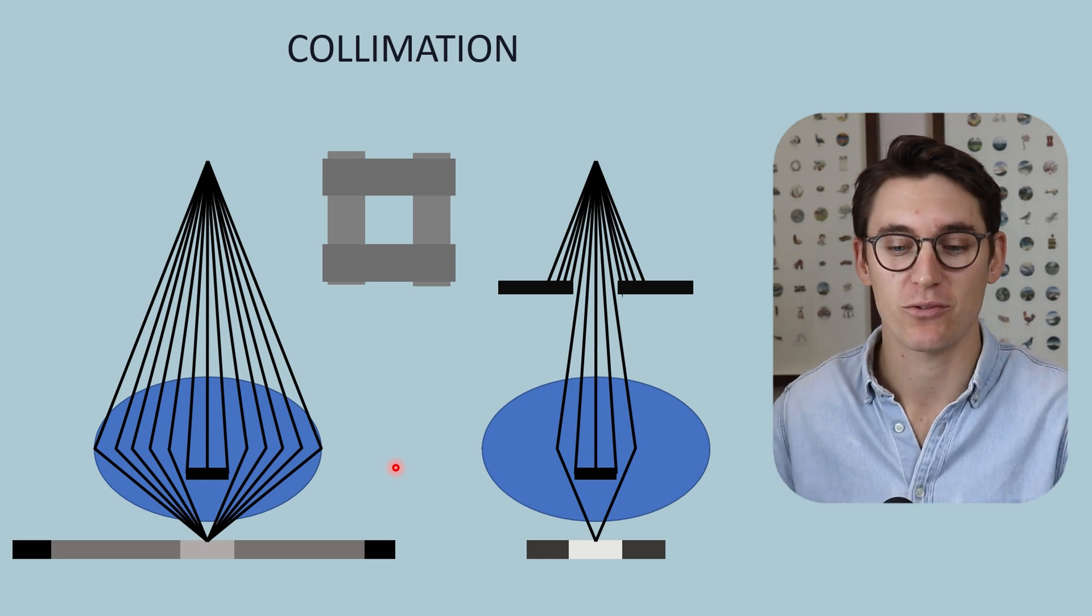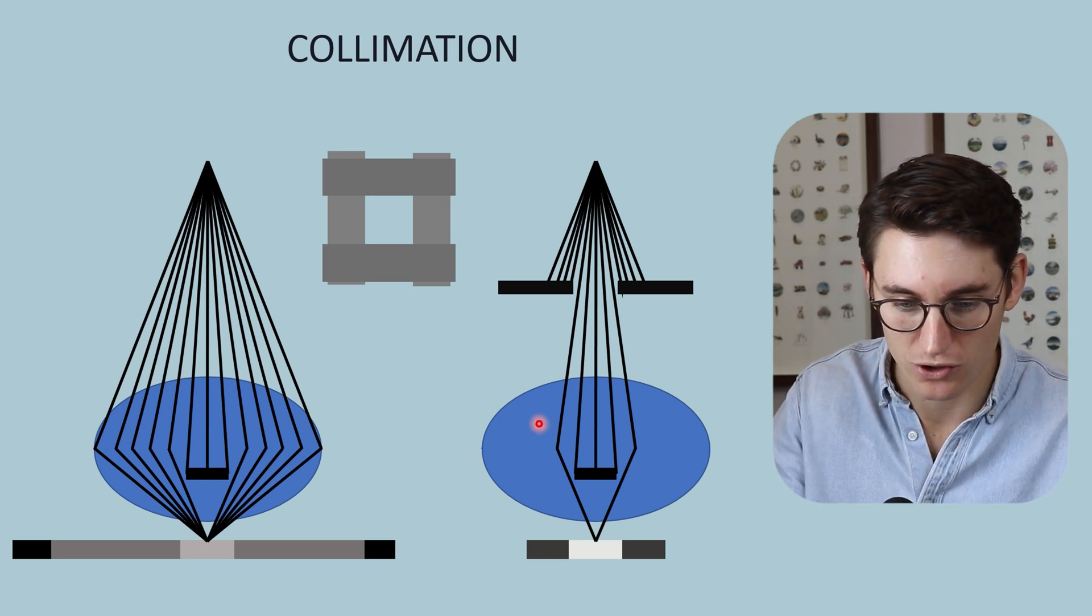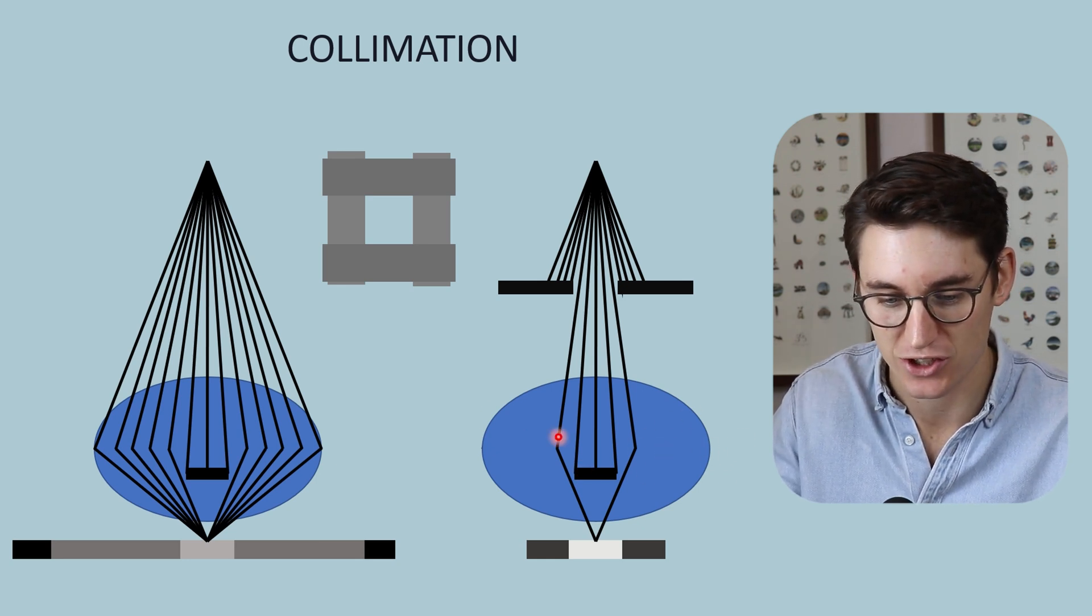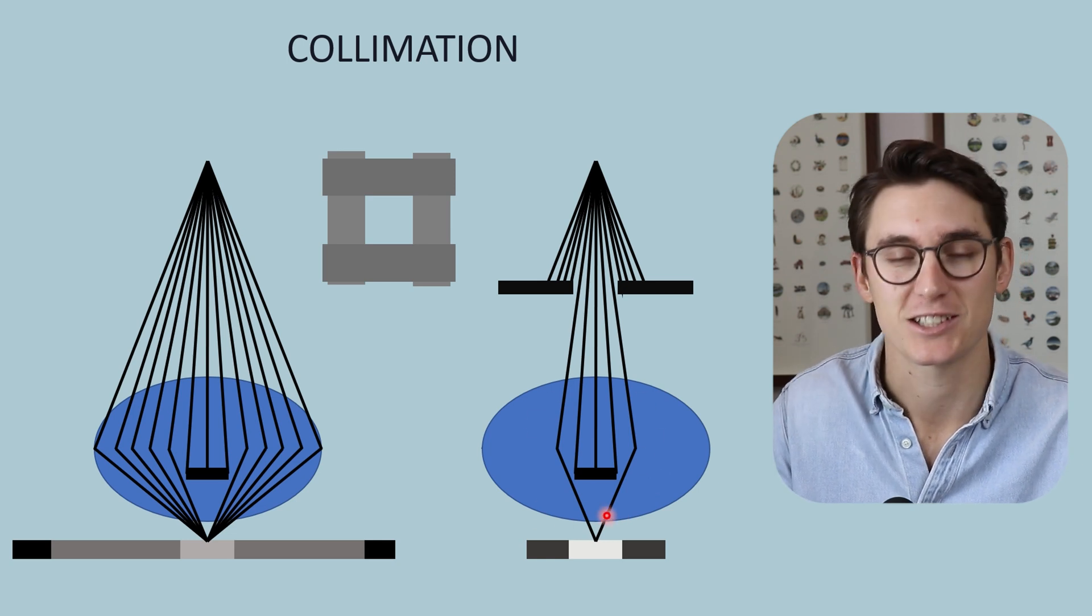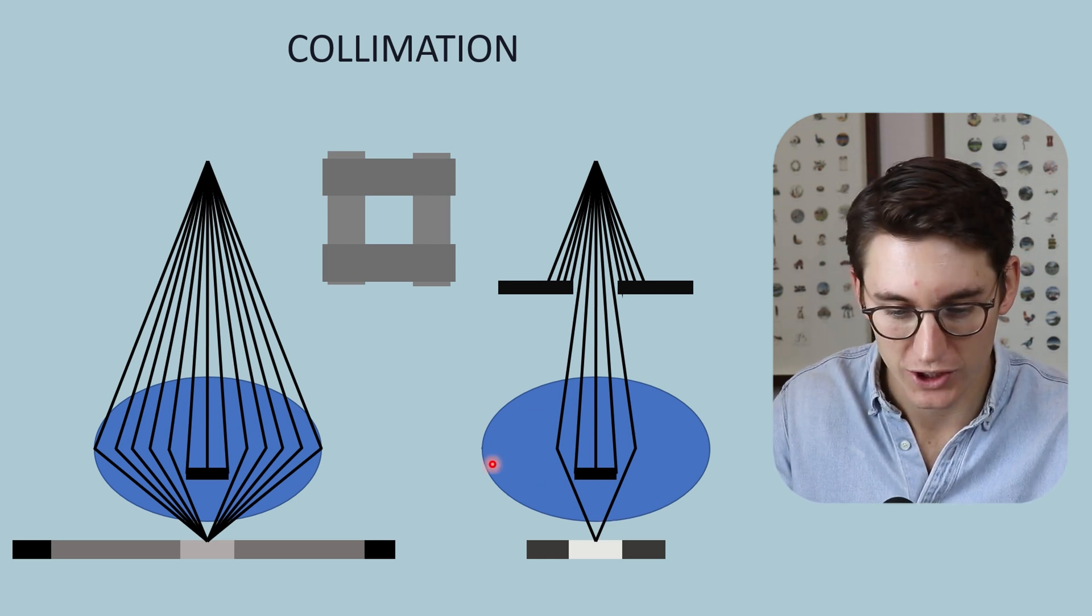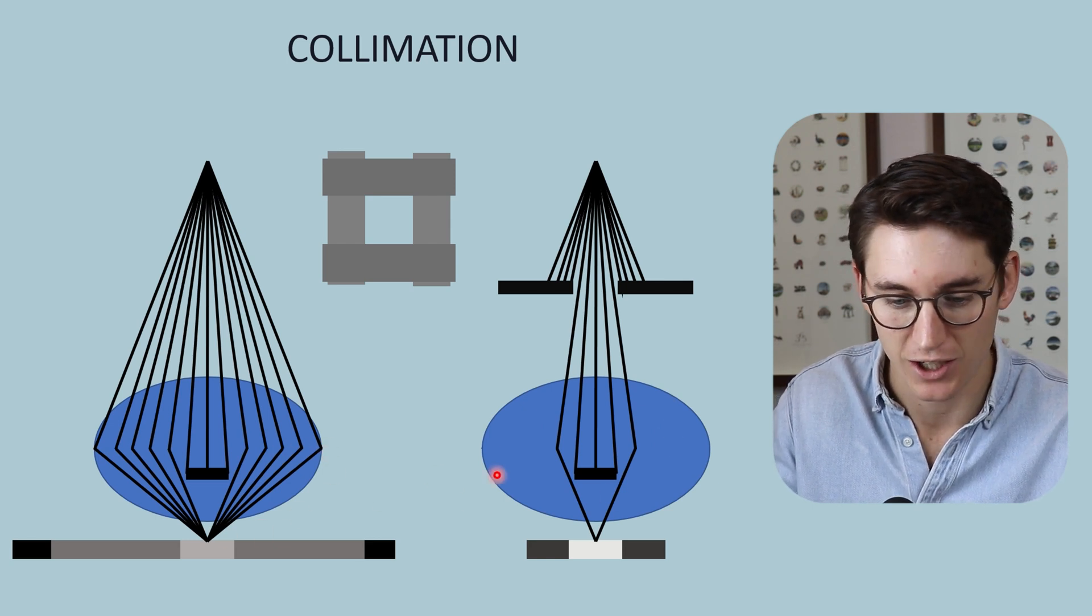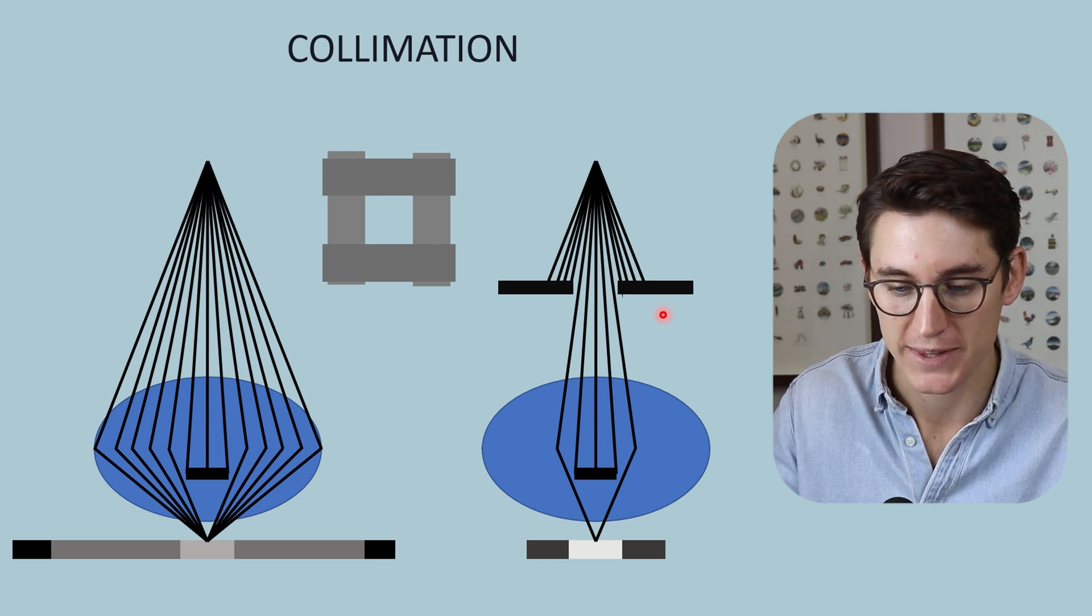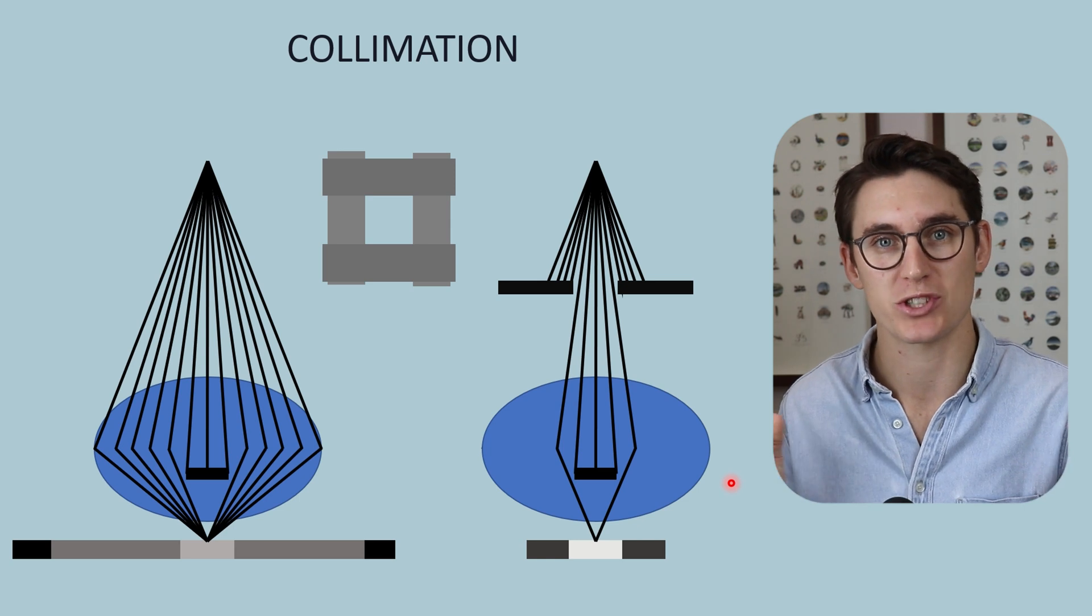If we collimate that field, we decrease the field size, we reduce patient dose because these regions of the patient are not getting ionizing radiation anymore. Only the region that we are looking at is exposed to x-rays. Not only do we decrease patient dose, but we have eliminated all of this scatter here. All of the scatter events that were occurring in these regions of our image no longer are occurring. And this is the best way that we can reduce scatter.